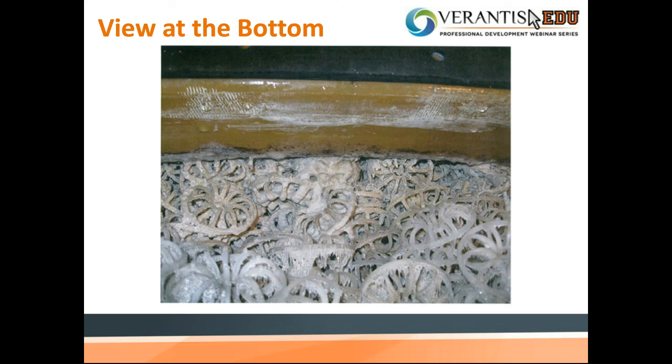So it's good to monitor temperature and pressure, maybe even pH and concentration in the scrubber, but really visual inspection is going to be the best method for monitoring your packing. I love that example. I like to refer to that as the beauty is only skin deep example. It really points out how easily you can look at just the surface and think that everything's fine, and truly illustrates how you have to dig in and get a feel for exactly what's happening throughout the whole tower with all of the packing. Exactly.